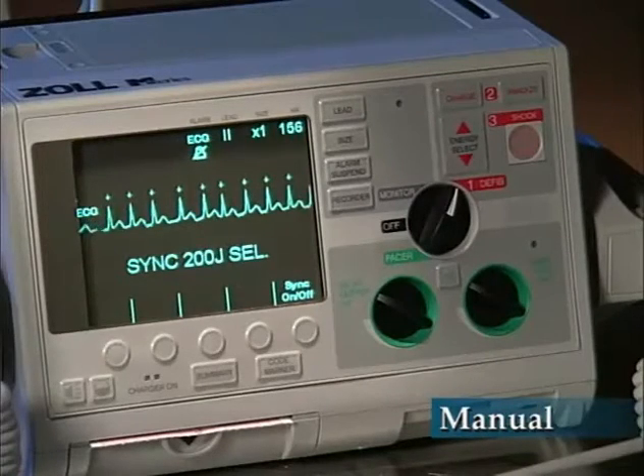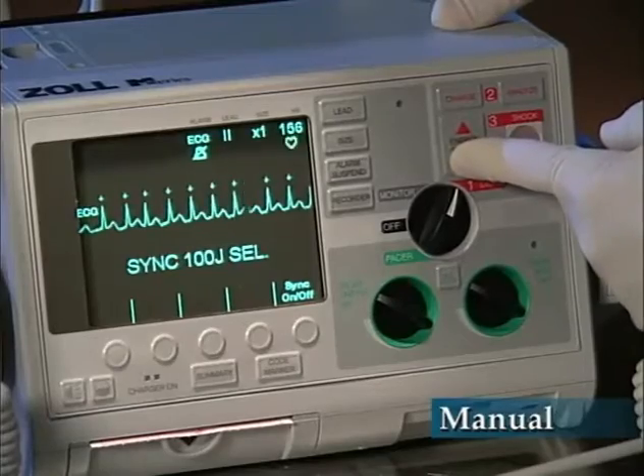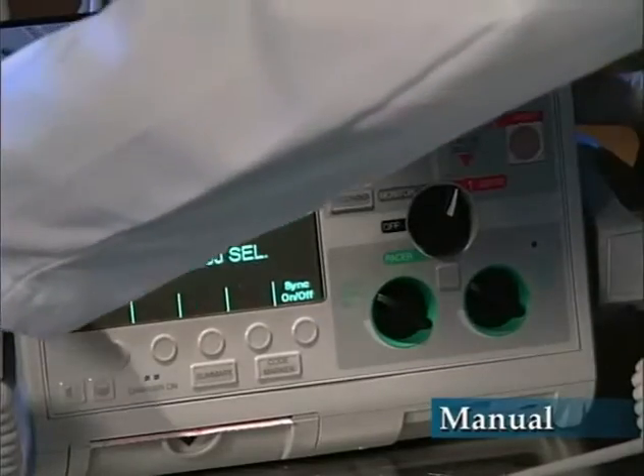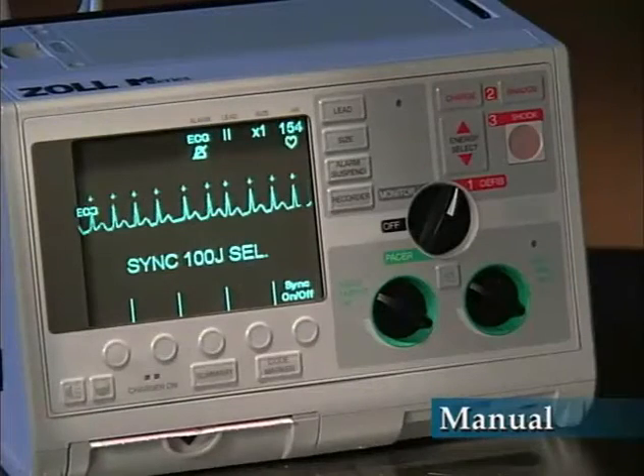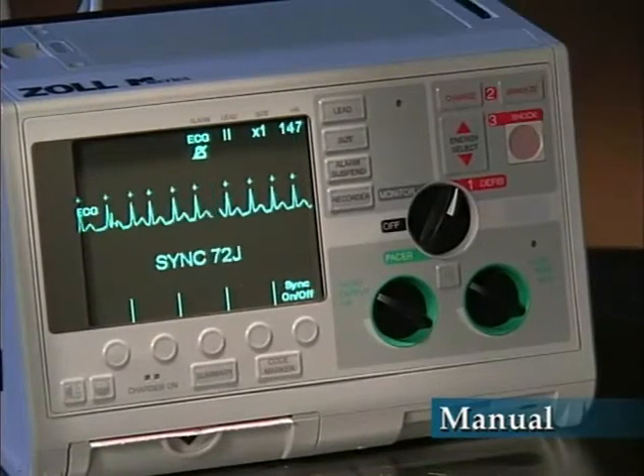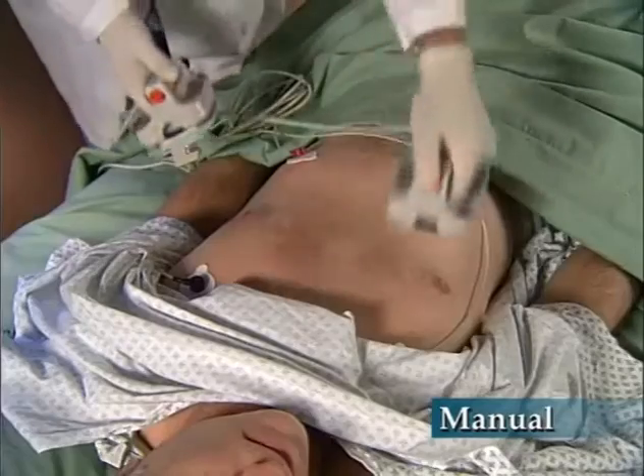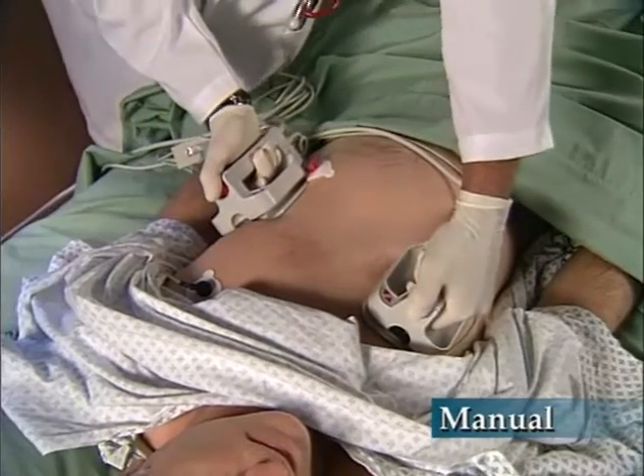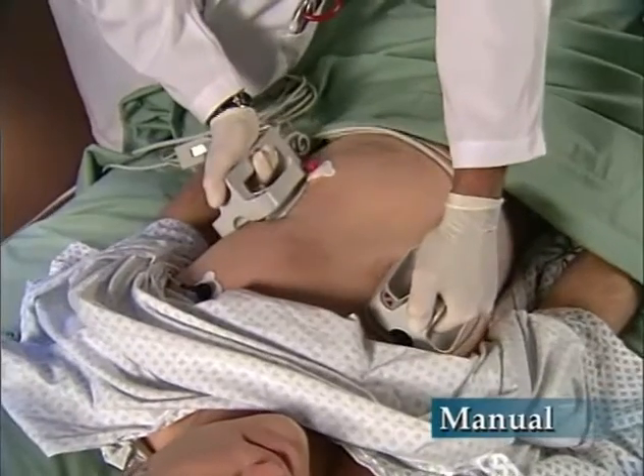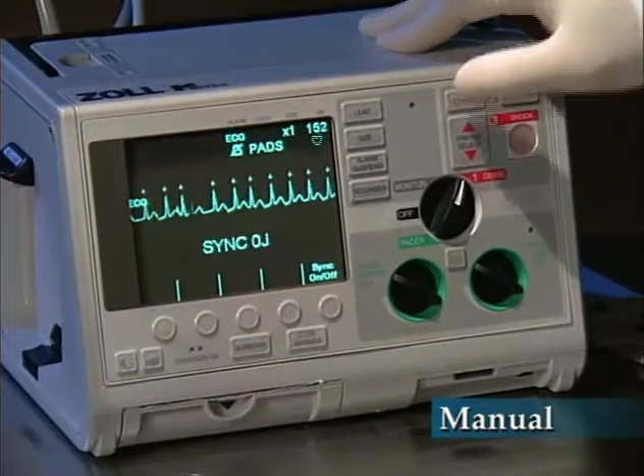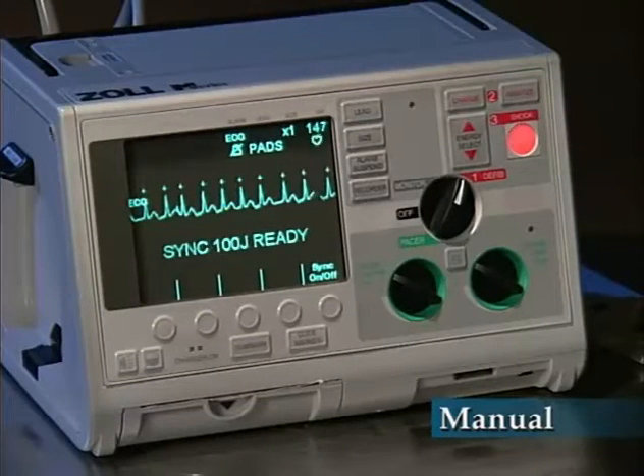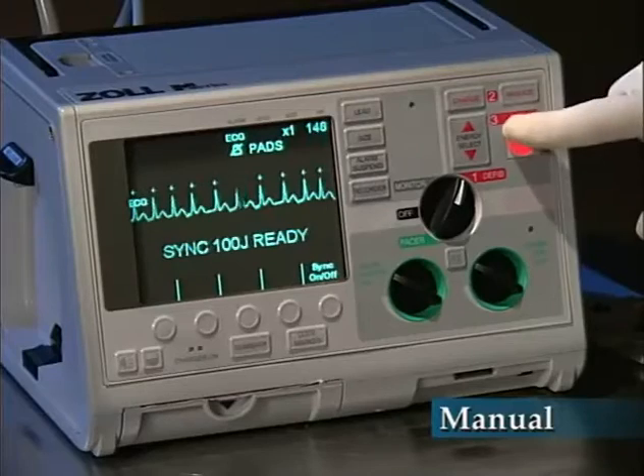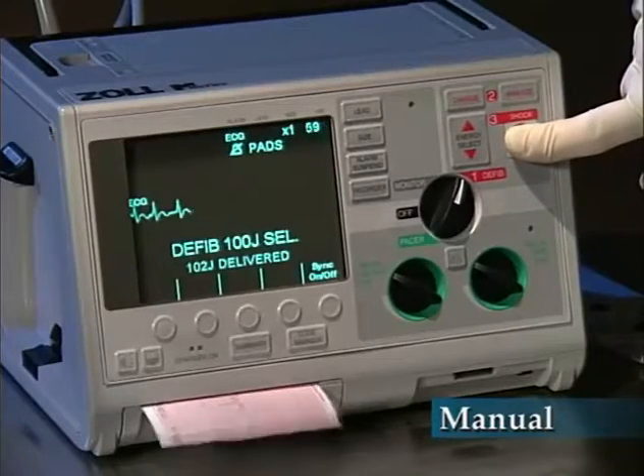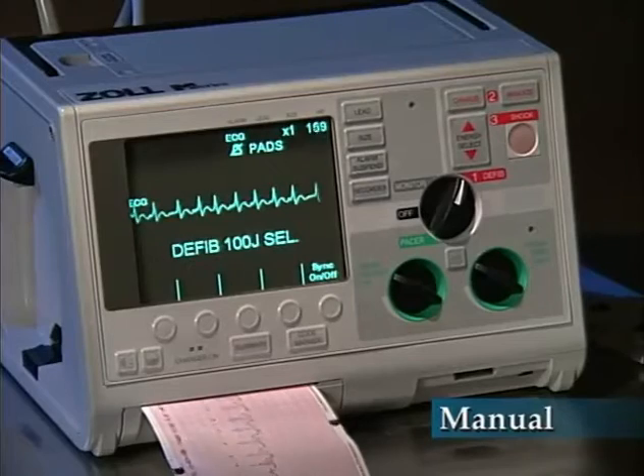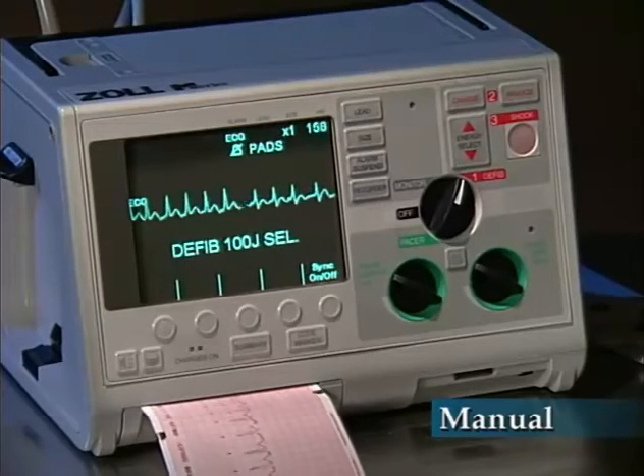Select the desired energy level. The word sync will appear next to the selected level. Using either paddles or multifunction pads, charge the defibrillator to the selected level. Verify the ECG waveform is stable. Clear. Deliver the synchronized discharge by depressing both paddles' discharge buttons, or if using multifunction pads, the shock button on the front panel. Press and hold the buttons long enough for an R wave to trigger a discharge. Clear. Once energy is delivered, the unit will automatically return to defib mode unless configured differently.